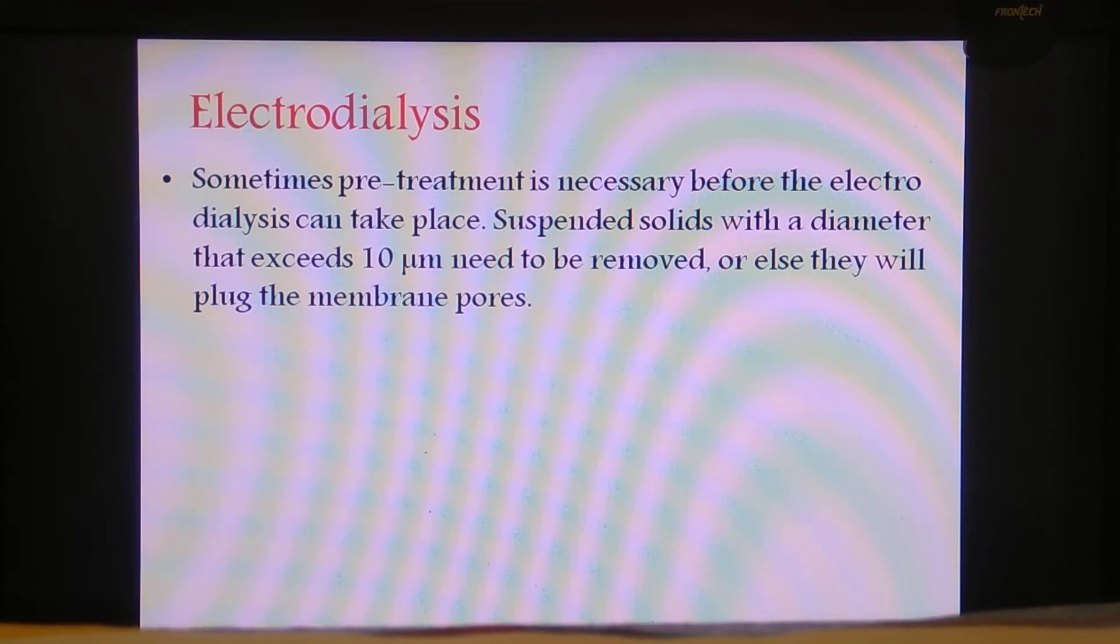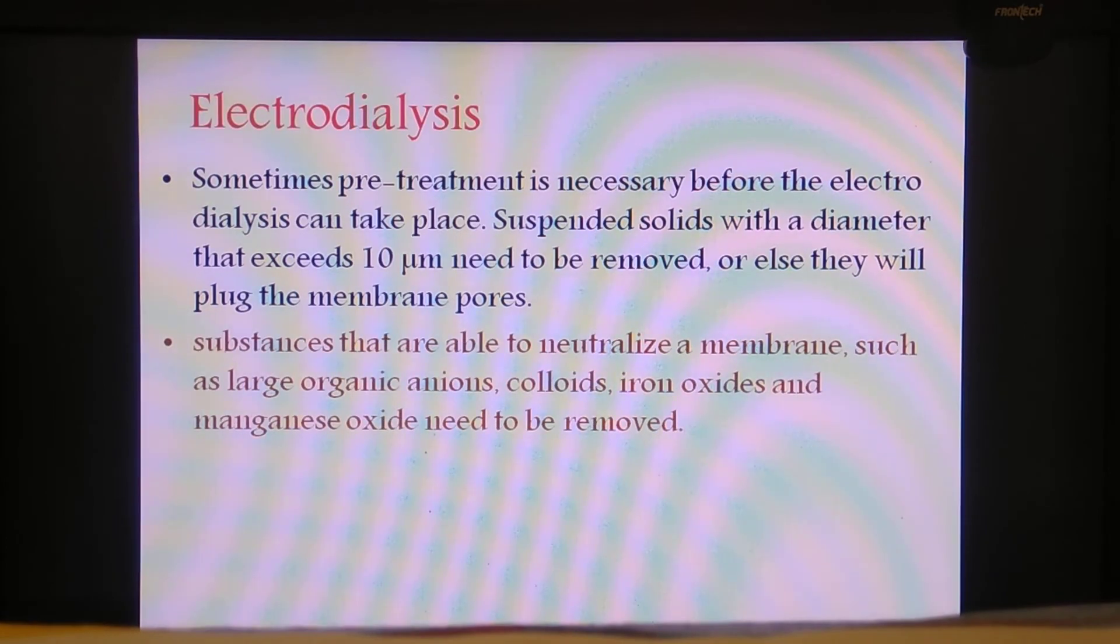Sometimes in order to carry out the phenomena of electrodialysis we require a certain pre-treatment. Before carrying out the phenomena of electrodialysis, we need to treat that water sample and remove the suspended solid material with a diameter that exceeds 10 micron by a simple phenomena of filtration. Substances that are able to neutralize the membrane, such as large organic anions, colloids, iron oxides, manganese oxides and dyes, need to be removed or else the membranes get tarnished.